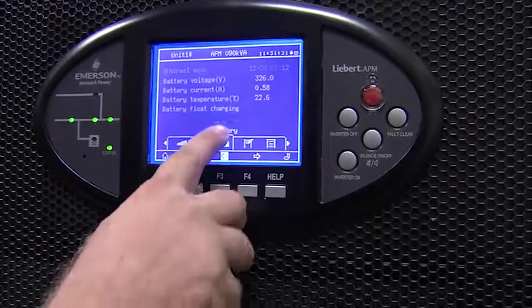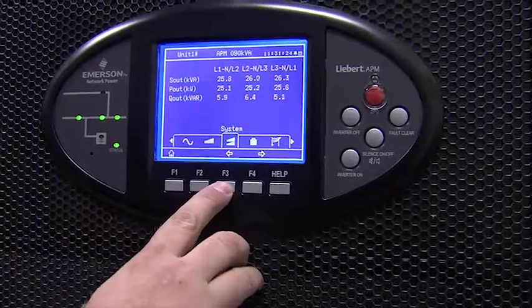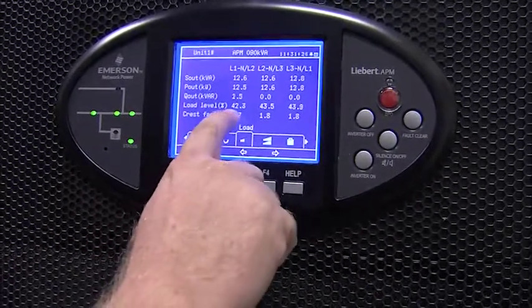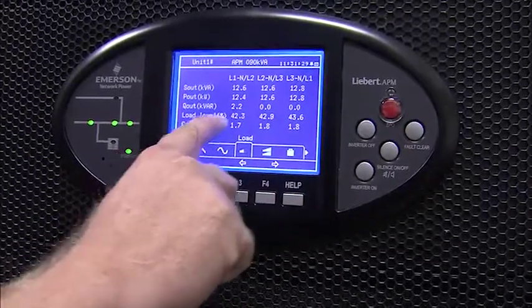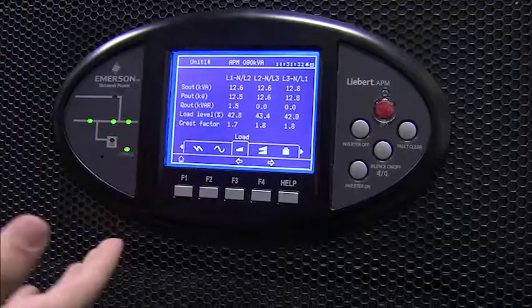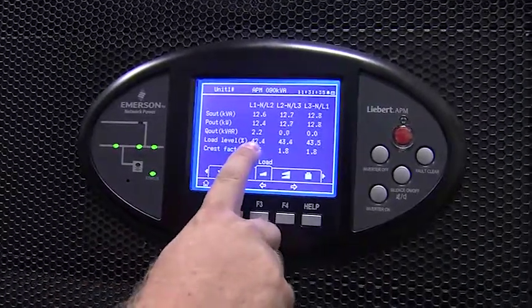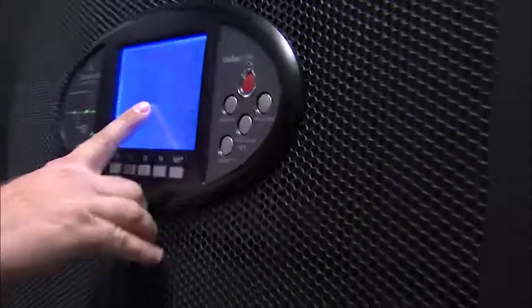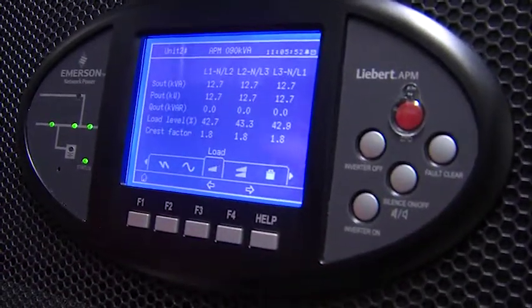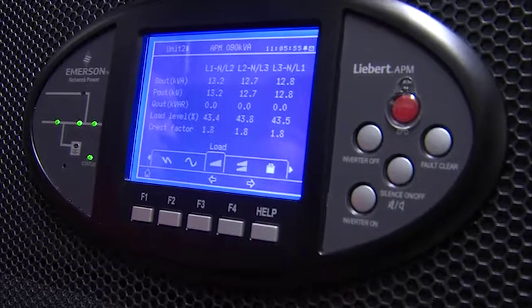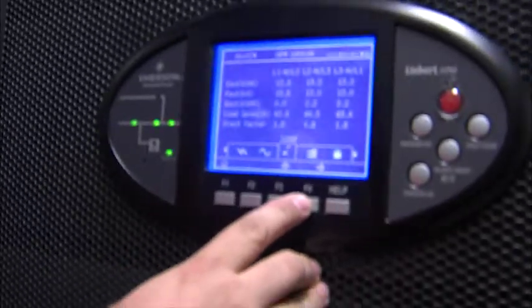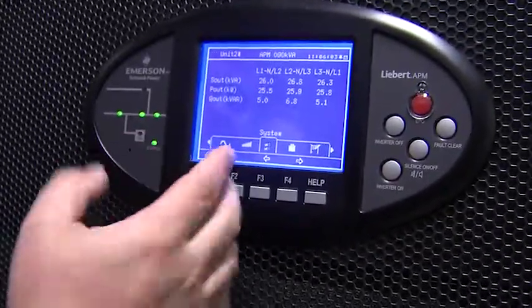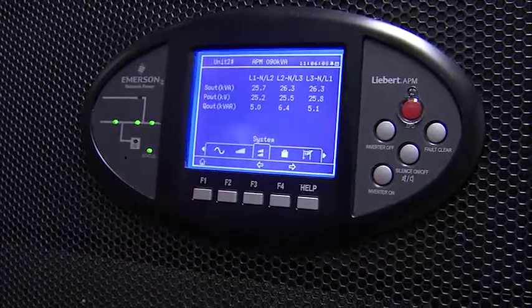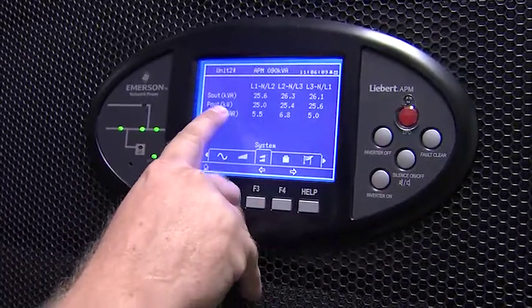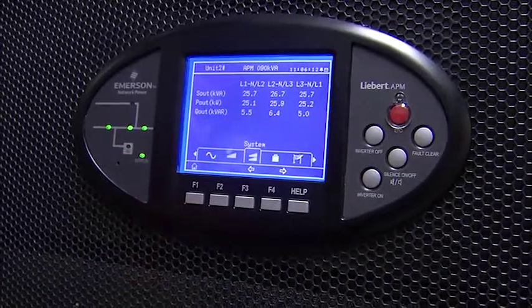And again, I'm going to scroll through the coordinated button. The load. So these should always be matching. Because they're sharing the load, this percentage here and this percentage here should be equal. If one unit was to fail, this whole load would go to that one UPS. We'll just continue here on this one. So I'll go to my next one, which is my system. That system is both units working together. So we have our 25 kW.